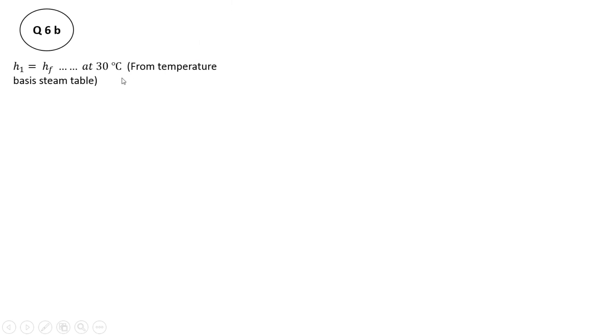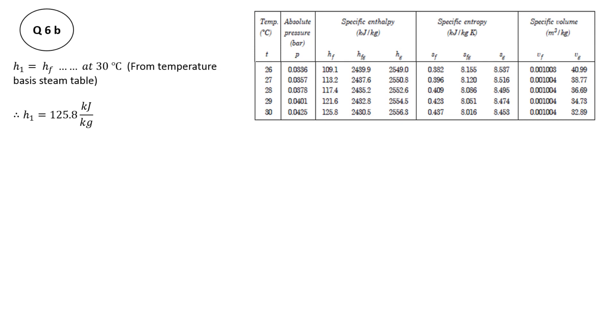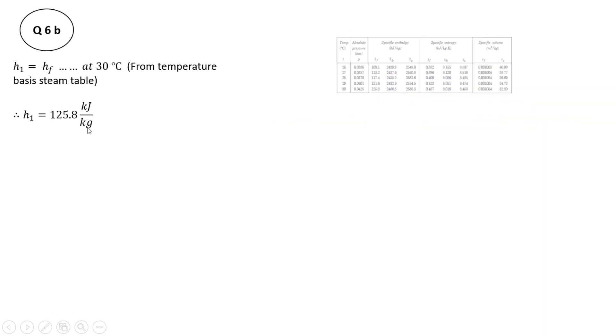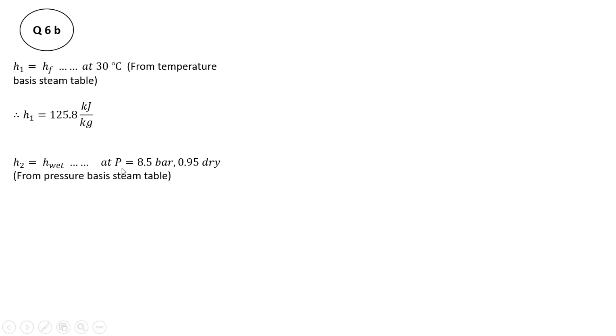Since feed water is supplied at 30°C, h1 equals hf at 30°C from the temperature-basis steam table — that is, the specific enthalpy of saturated water at 30°C. From the steam table, hf at 30°C is 125.8 kJ/kg. Then h2 is the enthalpy of wet steam, since steam is generated at 8.5 bar with a dryness fraction of 0.95, so it is wet steam.